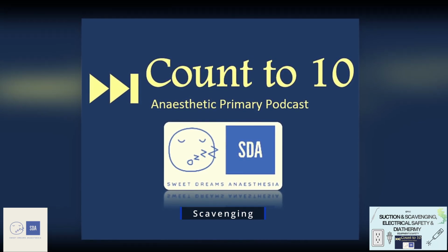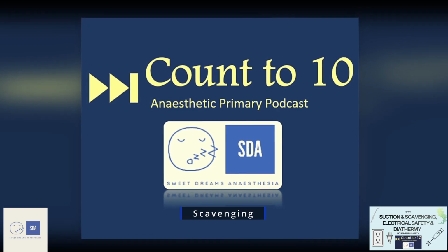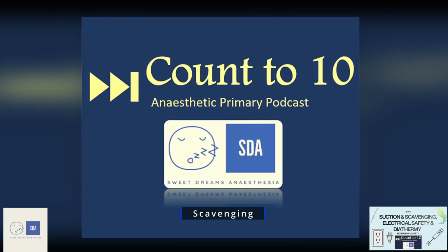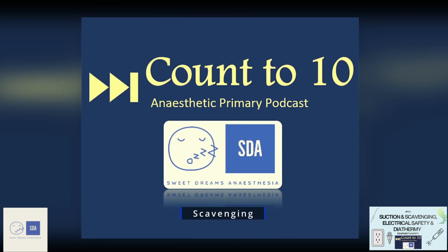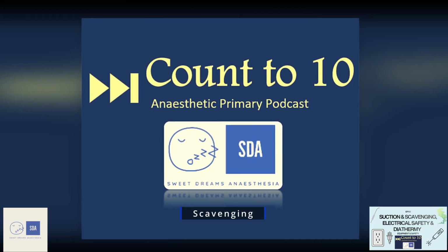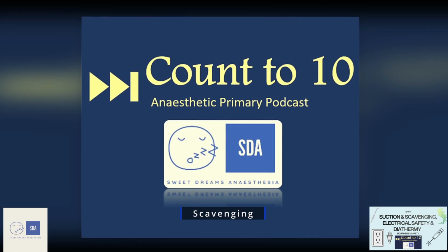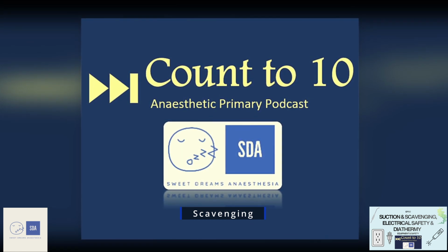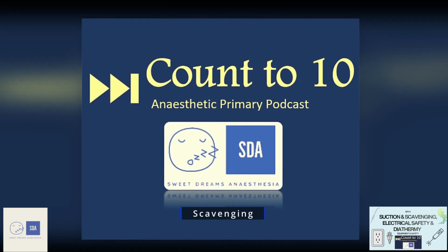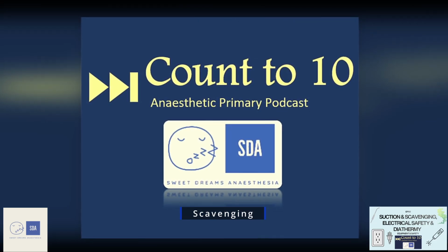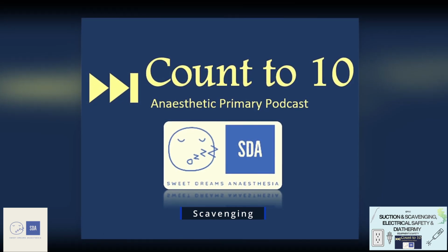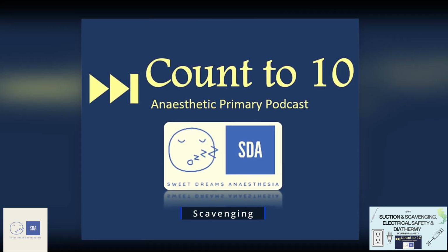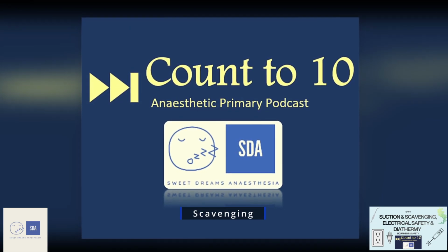Starting off with the collection assembly, which is where you collect the waste anesthetic gases. This is located within your breathing circuit next to your APL valve. It's prior to the CO2 absorber, and it's located there specifically so that waste gases may pass through the APL valve or the APL bypass valve if the ventilator is working, so that it doesn't collect the fresh gas that's been put into the circuit and it doesn't overload the CO2 absorber. And therefore, it's an ideal location to have your scavenging system.